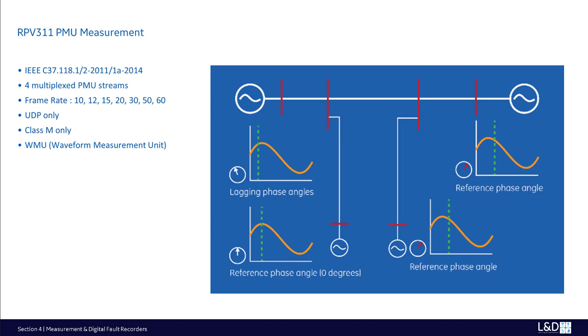The RPV311 can also be used for PMU measurement with remote acquisition modules according to IEEE C37.118 2011-2014 standards, like the DR60. Here are some differences with DR60. RPV311 has 4 multiplex streams. DR60 has 4 independent streams.